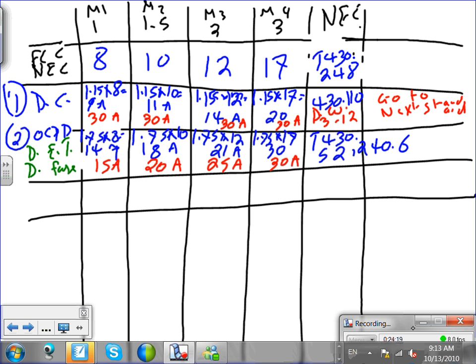Yes. I understand 14, 18, 21, 30, but what about 15, 20, 25, 30? Because these are not standard, because 21 is not standard, for the fuse or circuit breaker you go to 240.6 to find the standard. And all these red numbers are coming from 240.6. Any questions, my friends?